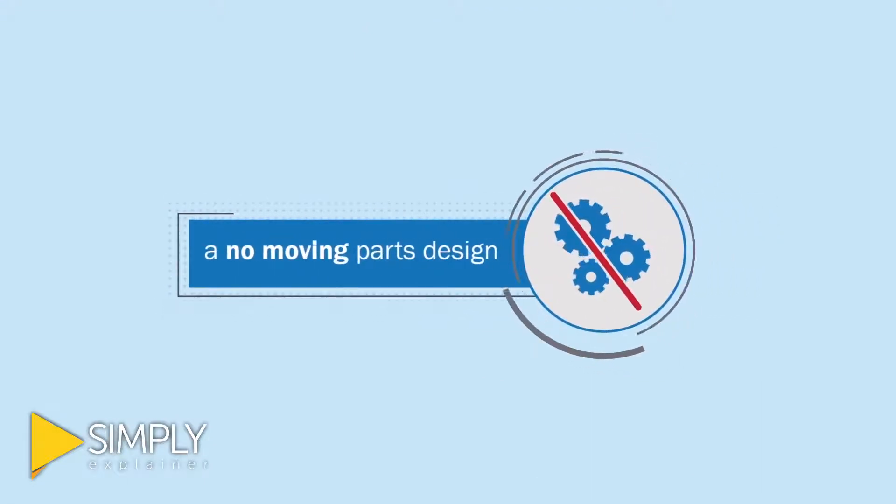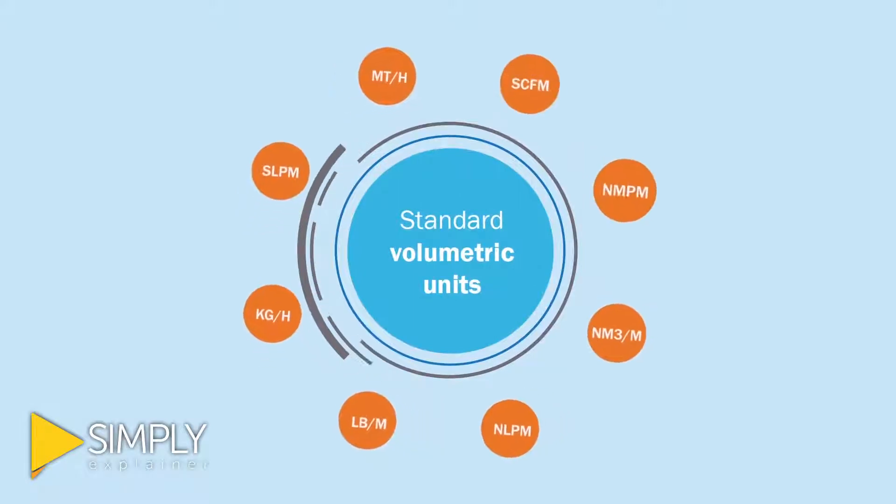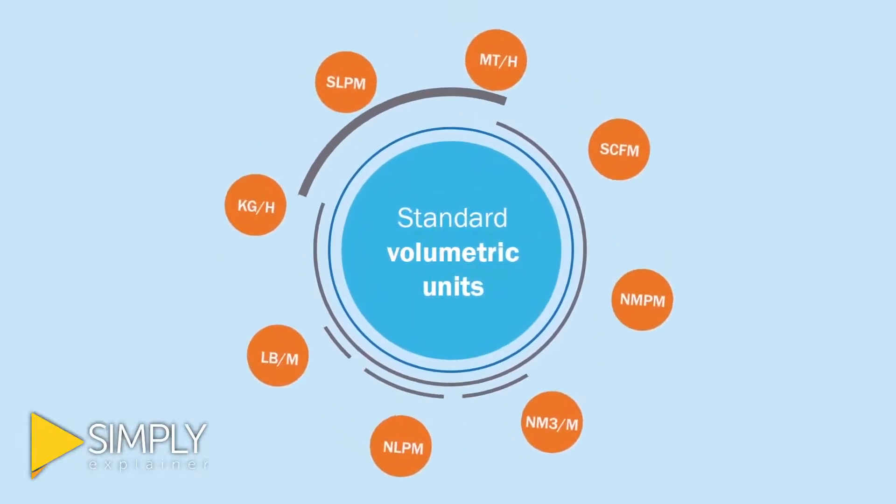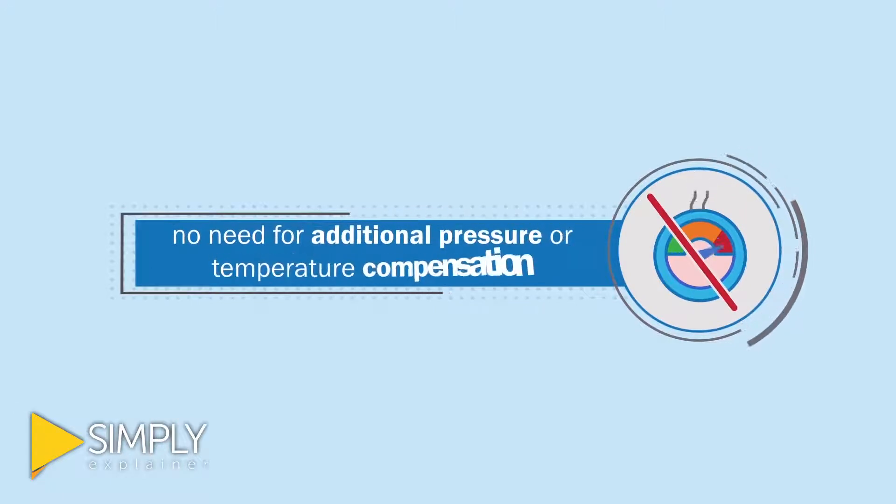All thermal mass flow meters operate under this principle. The benefits of this technology include a no moving parts design, the direct mass flow measurement of air and gases in standard volumetric units, and there is no need for additional pressure or temperature compensation.